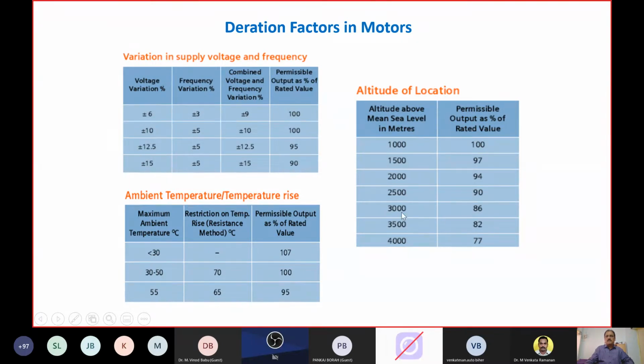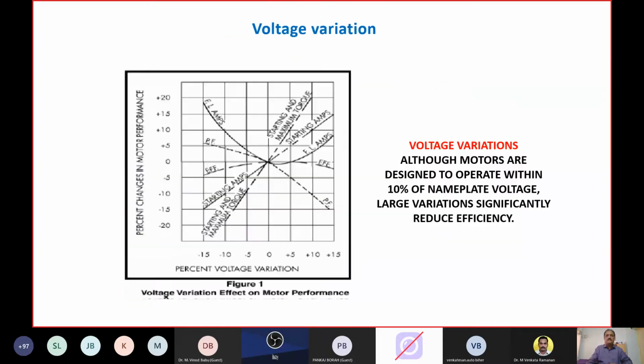For example, Ooty, which is 3000 meters above mean sea level, the derating applicable is 14%, or 86% of the motor rated power will be available at high altitudes. For those who might have entertained questions in their mind as to why in high altitudes the motor has to be derated, let me answer up front. The quantum of oxygen or the air density will be very, very low as you go up from the mean sea level. And therefore, since the air is the coolant medium for cooling the motor, there will be limitation in the cooling of the motor and therefore the derating.